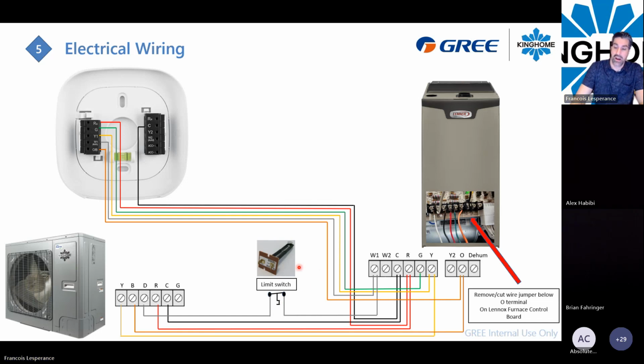This switch you can buy. This is not a part that Kinghome sells. You need to find your own limit switch, but you can find one that opens at 100 Fahrenheit. When you have a defrost call, you just pass the D signal in and out of the limit switch. So the furnace will be on, will be active, and when you hit 100 Fahrenheit, the furnace will stop.